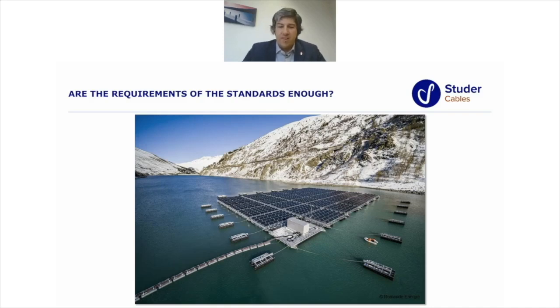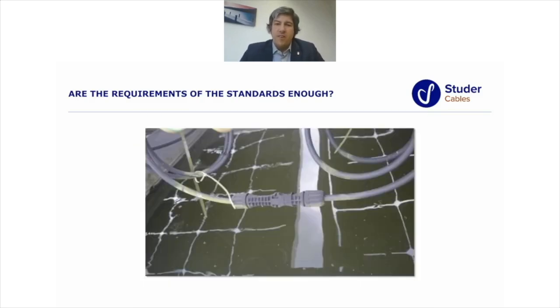What sort of problems? Let's take a look. Here you have, for example, the connectors with the cables, from time to time hanging in the water or dipped in the water. And here is one reminder from my side. In accordance with the specification of most connector makers, most of the connector warranty will be void in case of exposure to water for longer than 1 hour. What you see on the picture on the cable ends is nothing else than discoloration as a result of heat. The heat comes from the higher resistance inside the connectors. And what you see here is a very, very dangerous phenomenon.